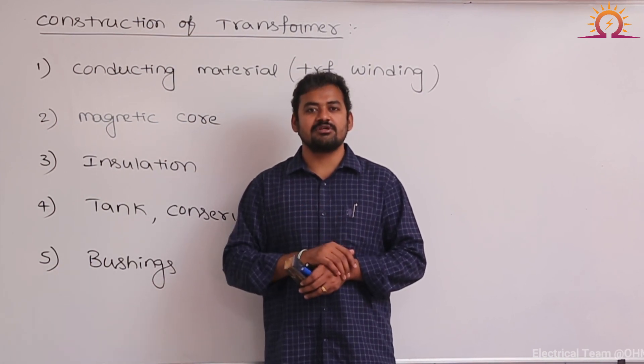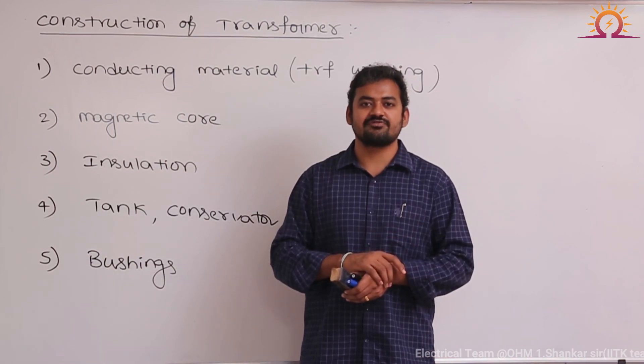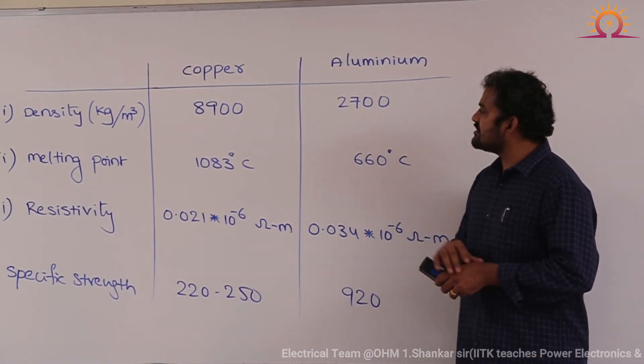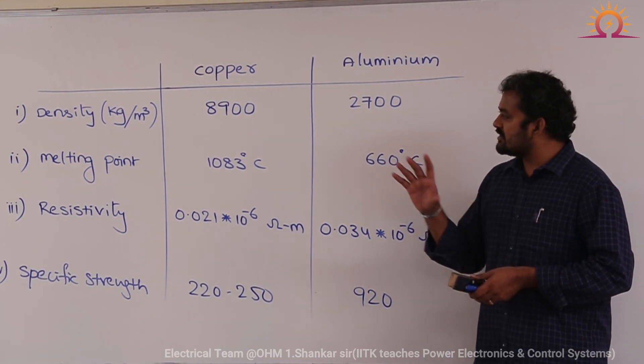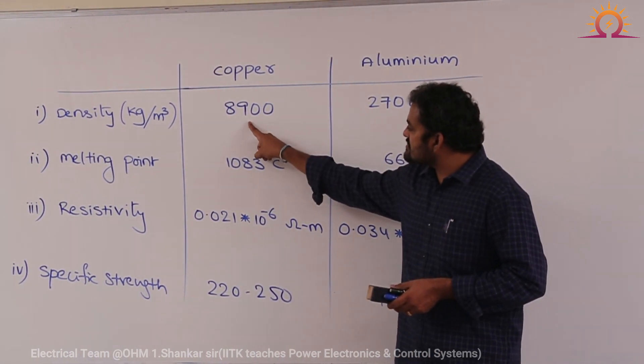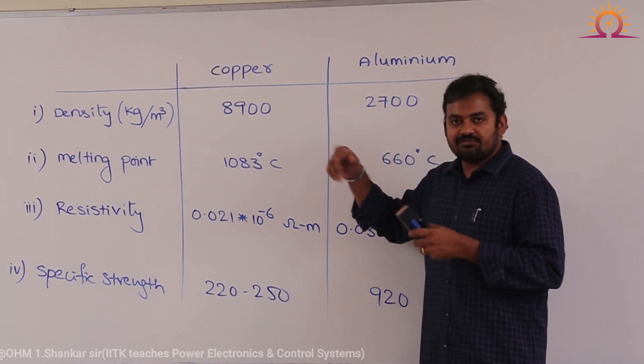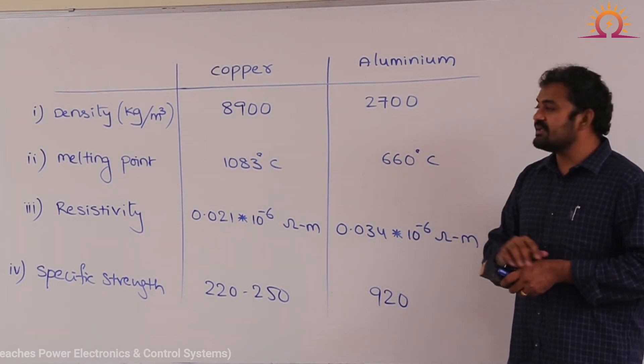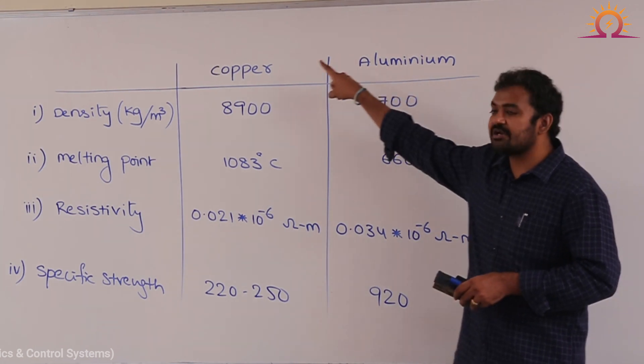Let us find out some differences between copper material and aluminum material so that we can decide which material is used for a transformer. There are so many differences, but these are the two major differences. Coming to the density point of view — that means the weight of the material — for a given volume, copper weight is 8900, aluminum weight is just 2700. For a given volume, copper winding weight will be almost three times more than aluminum weight. Also, aluminum is abundantly available on the earth's surface, and therefore the cost of aluminum is always less compared to copper material.